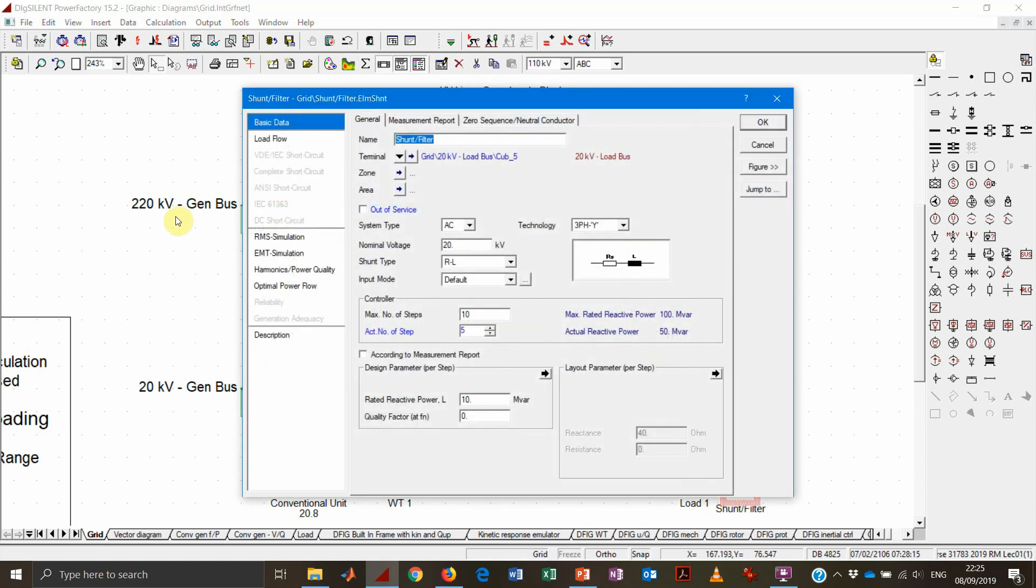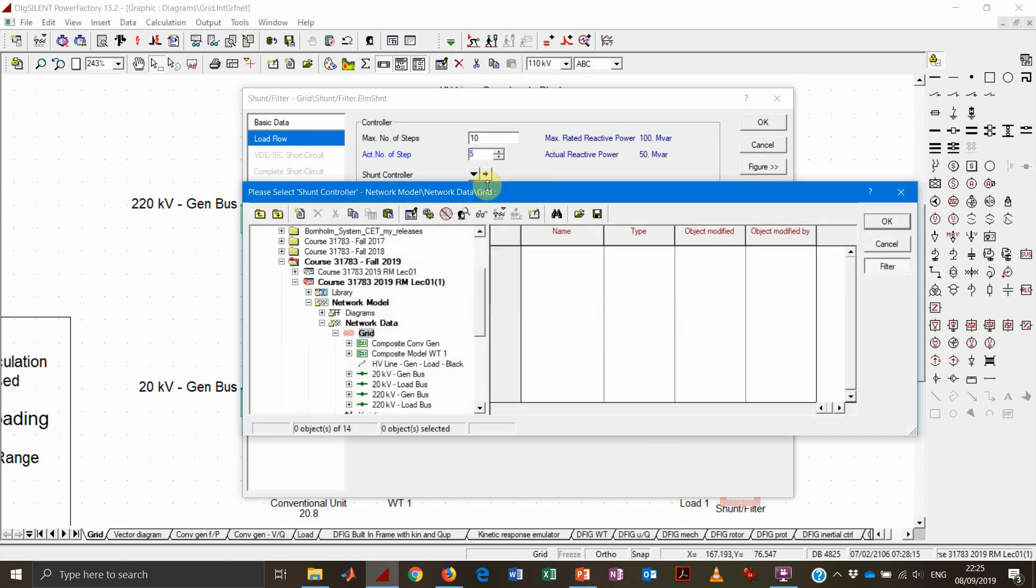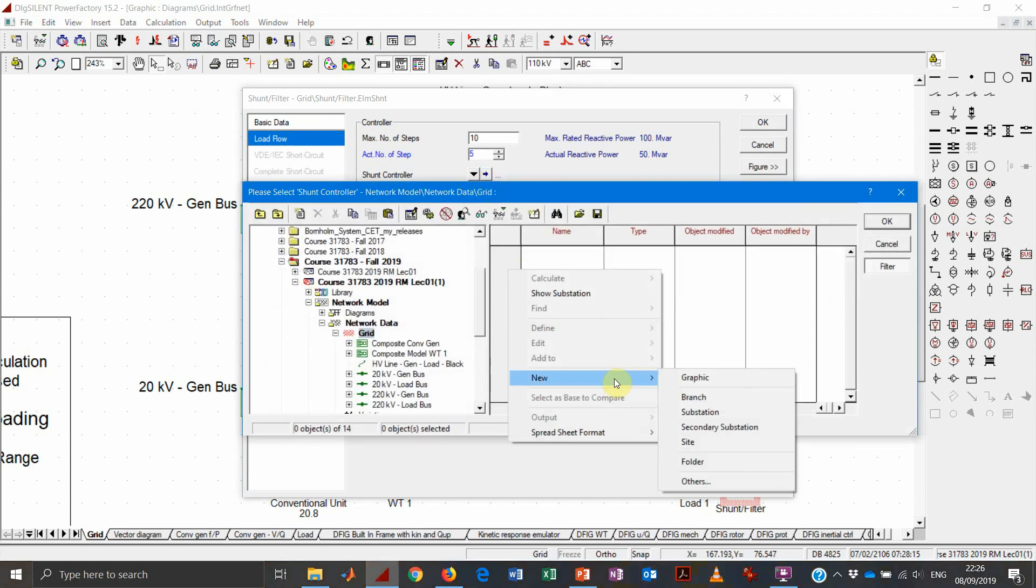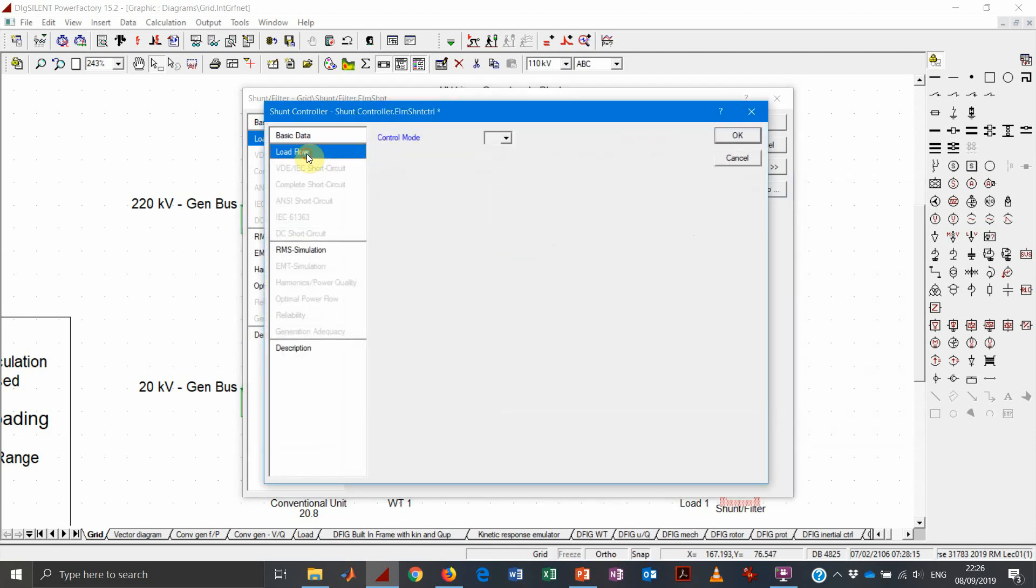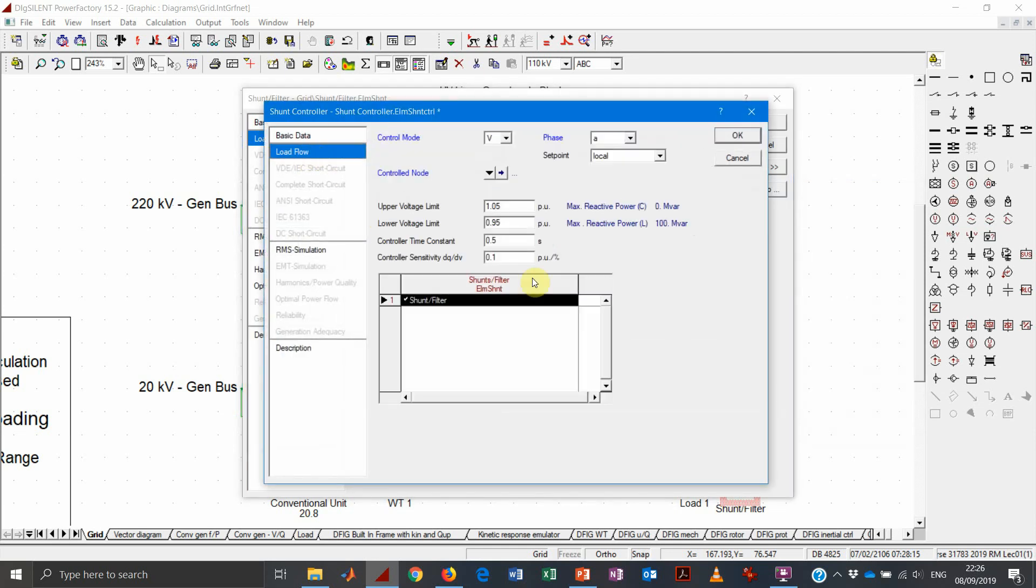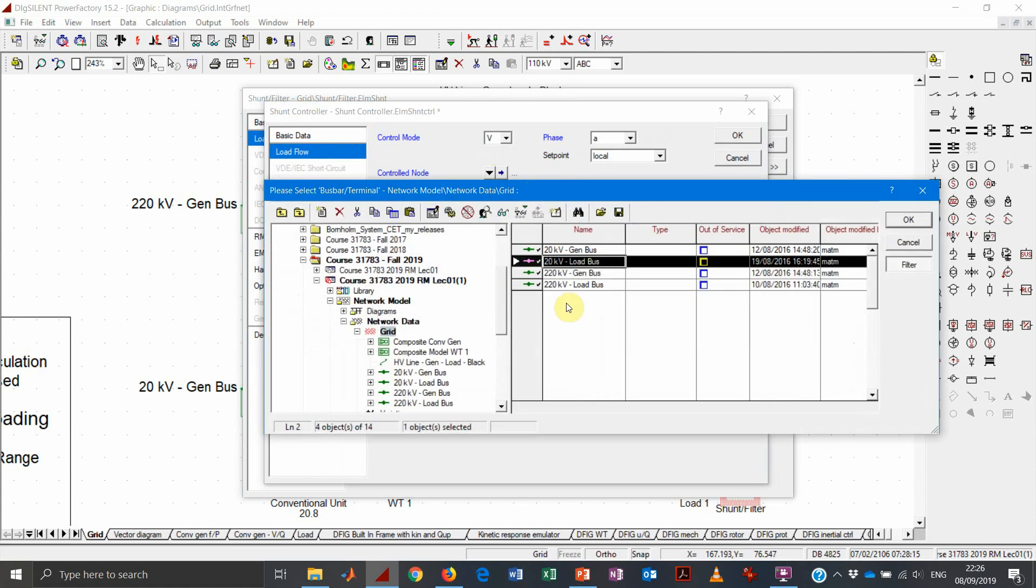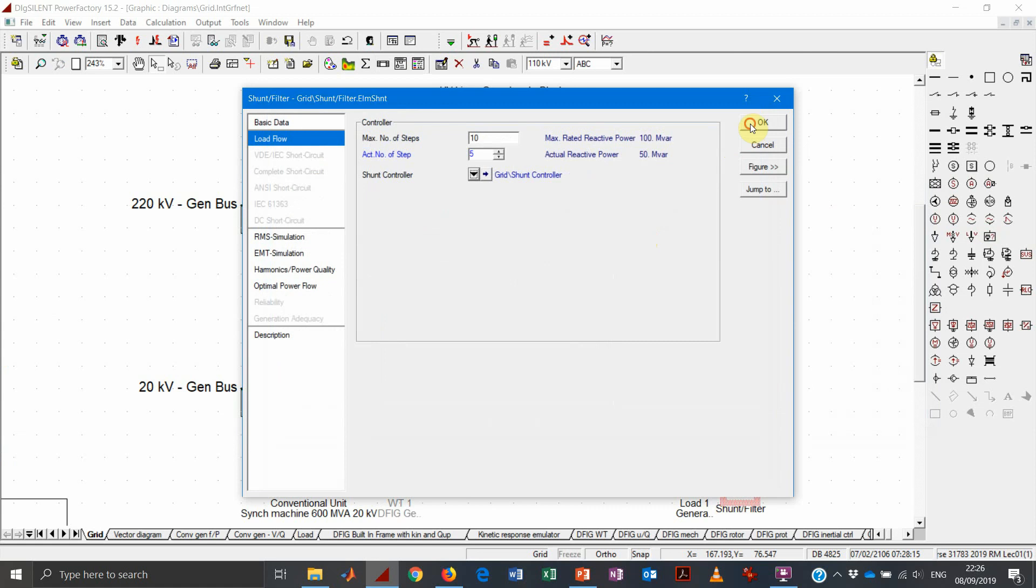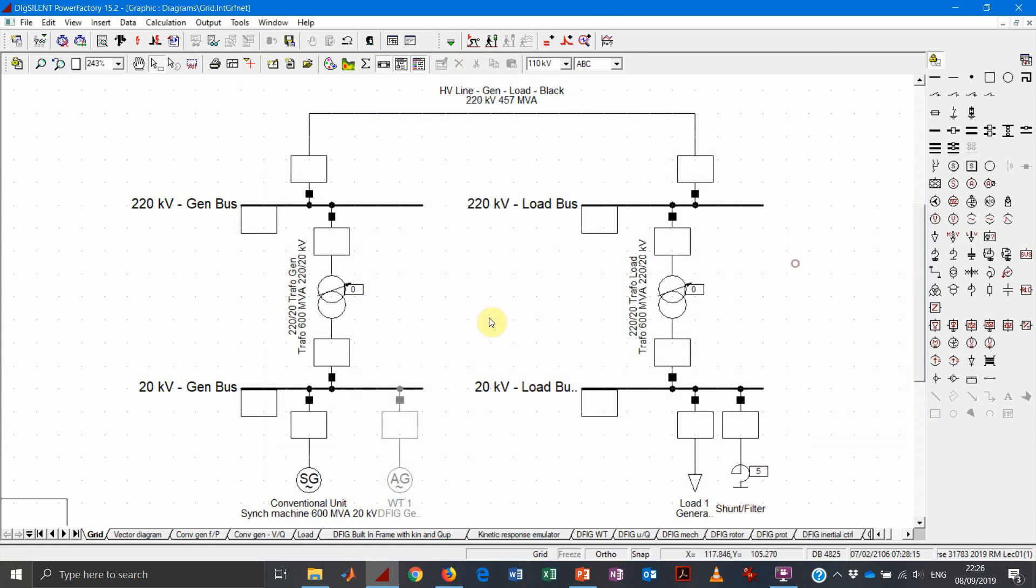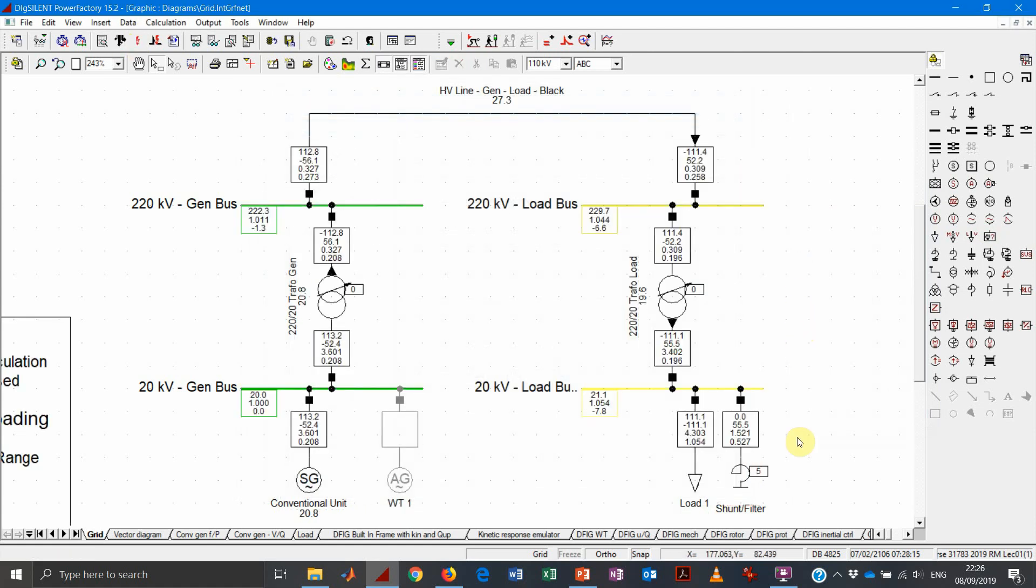We would like to see, in a bit smarter way, to have implemented a shunt controller so that we can actually dispatch the capacitor or the shunt in a proper way. So we can define a shunt controller, specify which node we would like to control, and then we run the load flow and see that nothing happened.